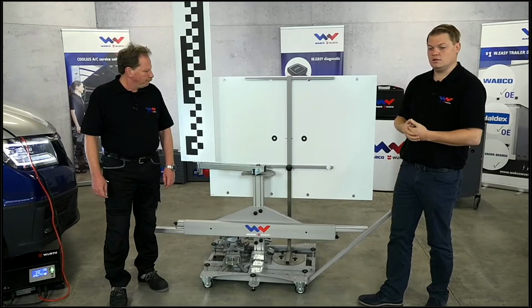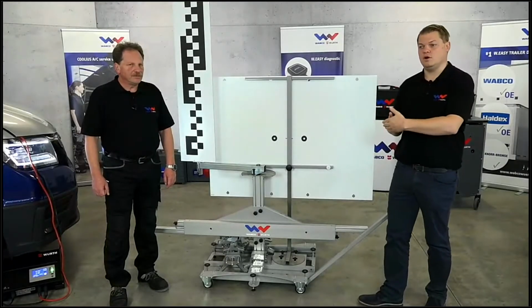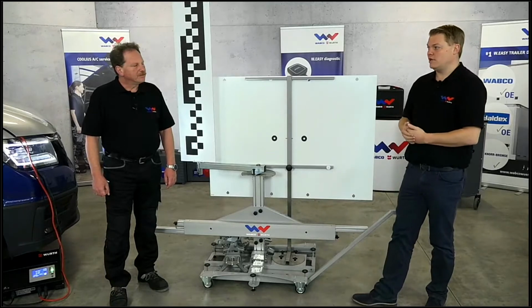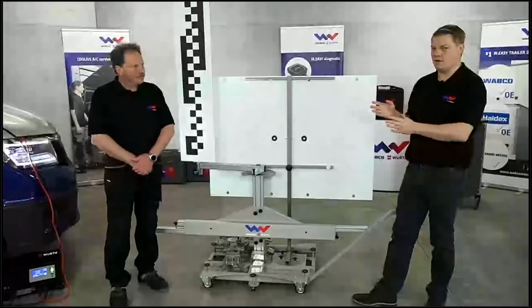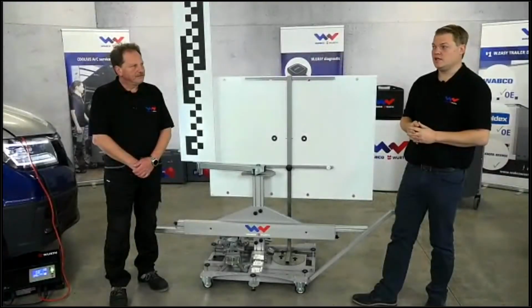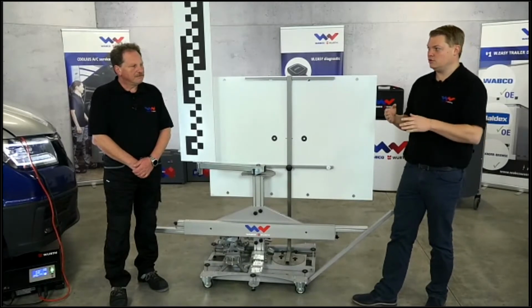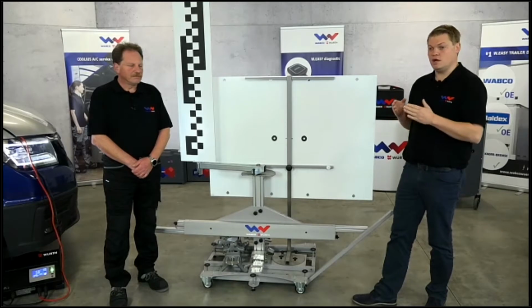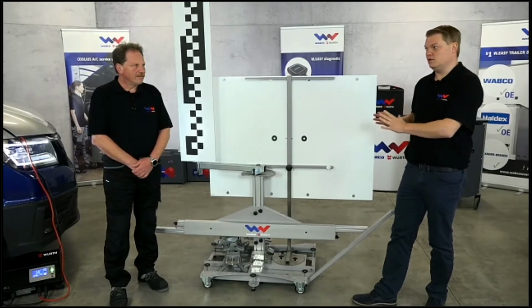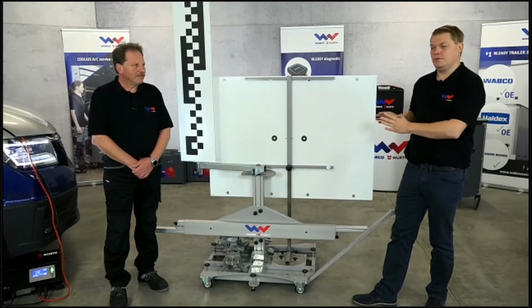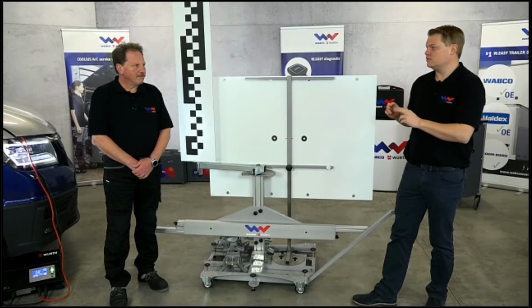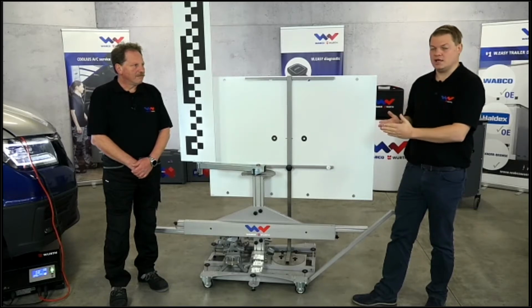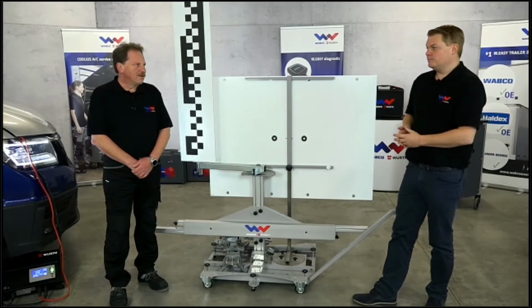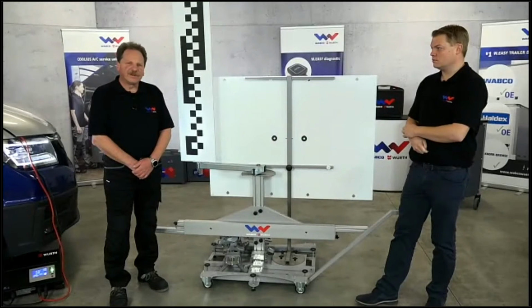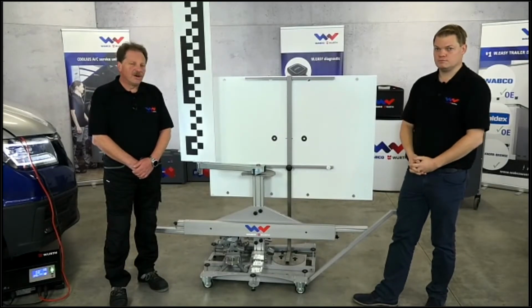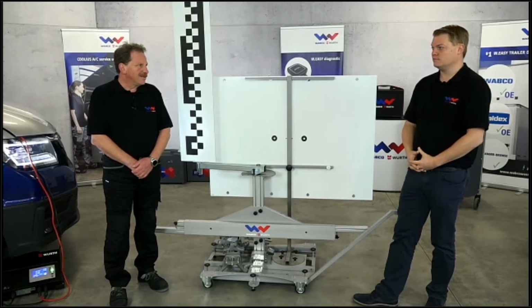Exactly. And this is defined in the instruction of the OE, of the original equipment manufacturer. They have clear guidelines that after such a repair, the camera has to be calibrated. The way it has to be calibrated is clearly written in our software, because our software fulfills the OE standards. So you are absolutely on a secured side of how to calibrate, and that the job has been done with a tool that is aligned with the OE regulations. Also, as we are using our software in that case, you will receive a documentation of the successful calibration. Exactly. That's needed afterwards.